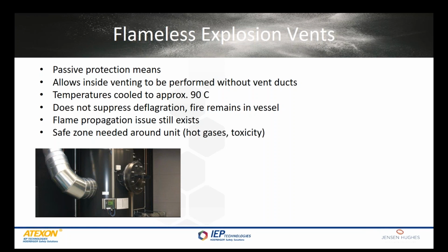Flameless vents, there's two basic styles of flameless vents. There's a rupture panel style flameless vent, and then there's a spring-loaded style flameless vent with a plate that moves at a certain pressure. Both styles have basically a flame arrestor around the outside of them, so that when the overpressure from the explosion causes the vent to open up, the heat from the flame is absorbed as a heat sink through the flame arrestor, and then all that's ejected is hot gases. Those hot gases are basically cooled to somewhere around 160 to 200 degrees F. And there's no flame that then is released into the room.